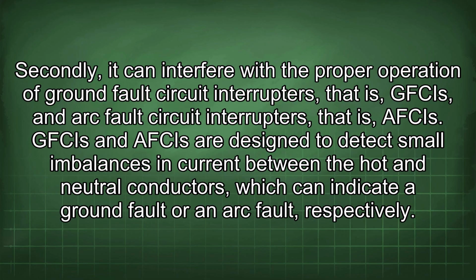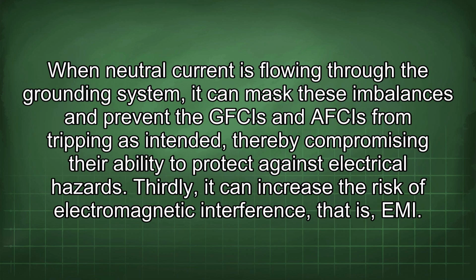Secondly, it can interfere with the proper operation of ground fault circuit interrupters, that is, GFCIs, and arc fault circuit interrupters, that is, AFCIs. GFCIs and AFCIs are designed to detect small imbalances in current between the hot and neutral conductors, which can indicate a ground fault or an arc fault, respectively. When neutral current is flowing through the grounding system, it can mask these imbalances and prevent the GFCIs and AFCIs from tripping as intended, thereby compromising their ability to protect against electrical hazards.